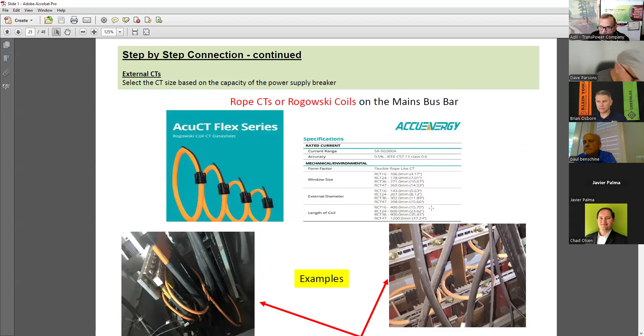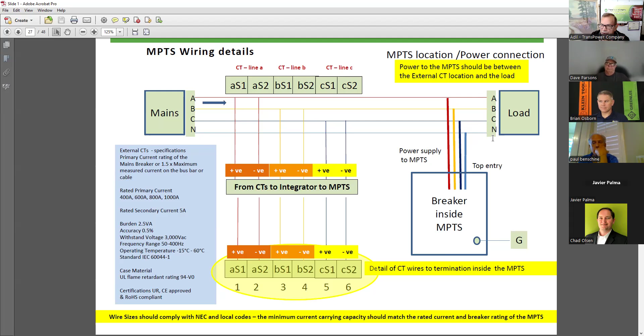So what happens when an error like this occurs? You have CTs inside the MPTS tracking what's happening on the load side, but it's already accounted for here. When you install these CTs here, both CTs end up reading the same thing. This is a common mistake in installations when people aren't paying attention, they just think, 'this bar goes from here to here anyway, how does it matter?' It'll become a little clearer as I go through.